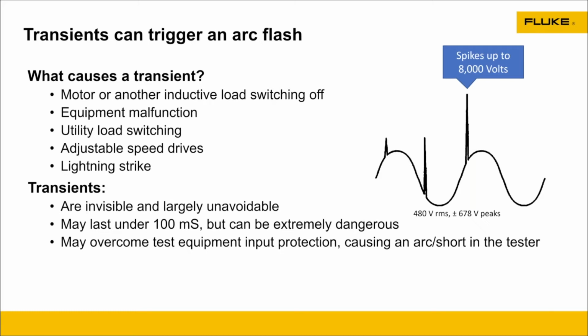And what causes that? Could be inductive gear switching on and off. Maybe there was a malfunction in equipment. Maybe there was a utility load that was switching at the time as well. Even adjustable speed drives can cause some of those transients. And it's pretty obvious if you had a lightning strike, yeah, that's a lot of energy. I think I've seen Back to the Future. We've all seen Back to the Future. Yeah, it's a massive amount of energy that's going to be running through that to cause that type of transient.